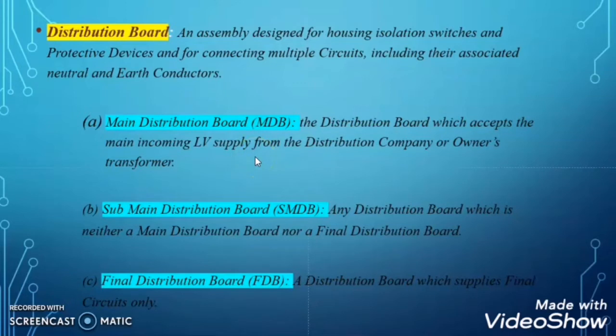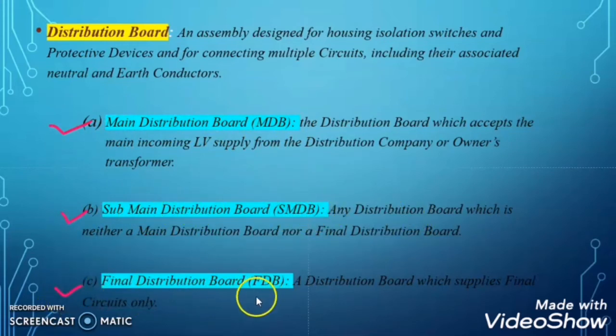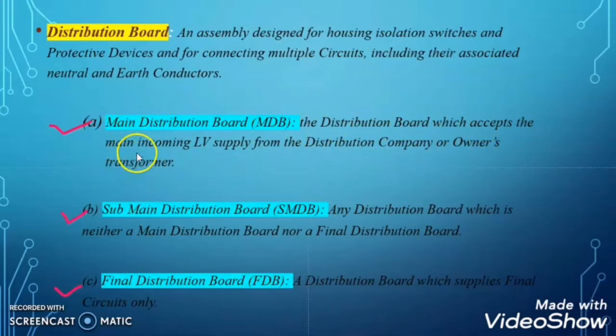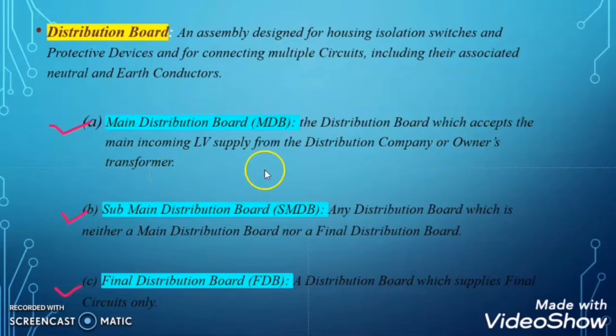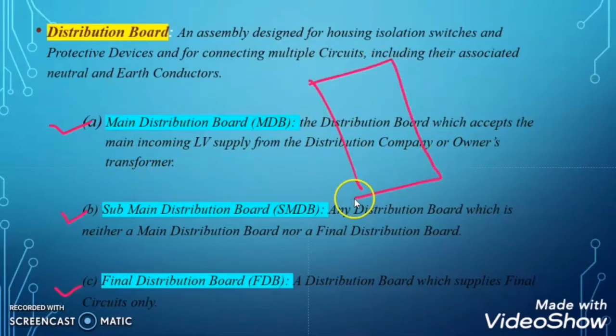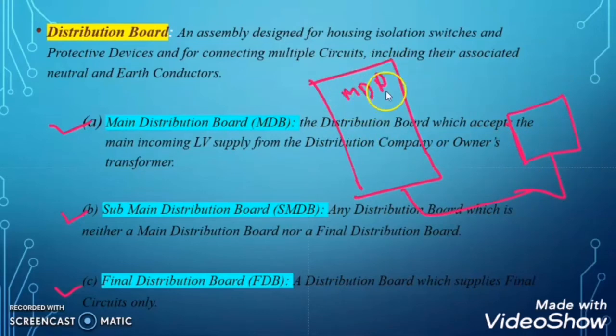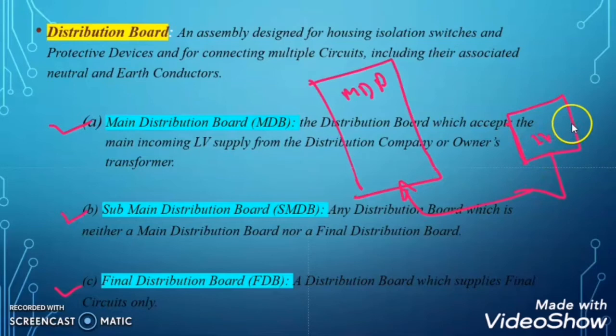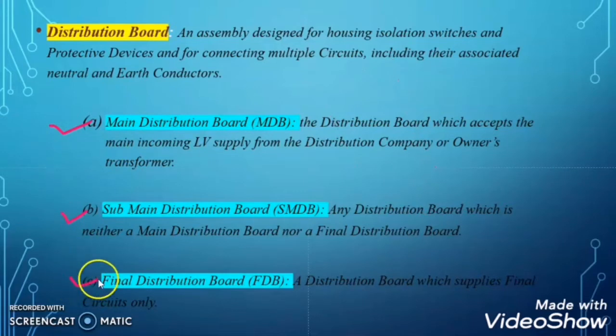Mainly there are three types of distribution board. The first one is main distribution board (MDB), the second one is sub-main distribution board (SMDB), and the third one is final distribution board (FDB). The distribution board which accepts the main incoming LV supply from the distribution company or from a transformer is called the main distribution board. When a distribution board takes power directly from the LV side of the transformer, that panel is called the main distribution board.